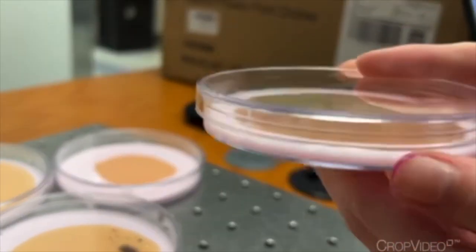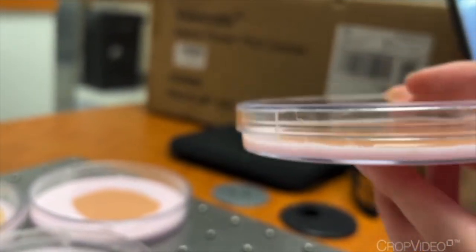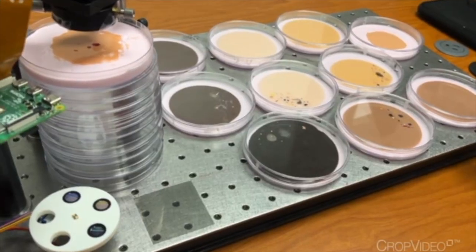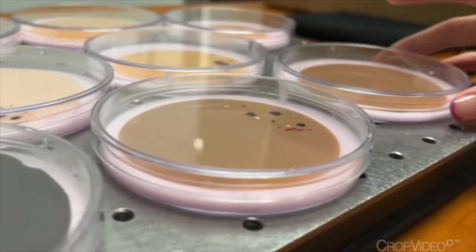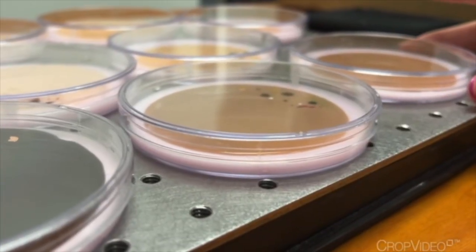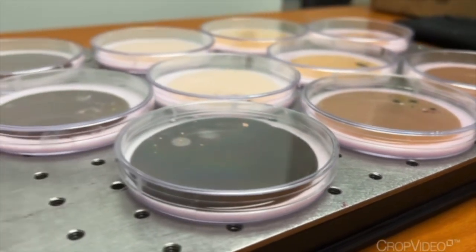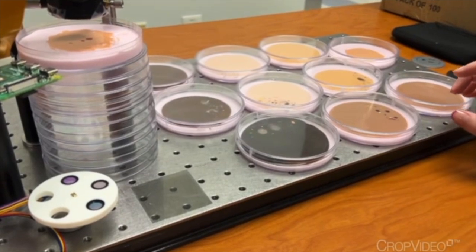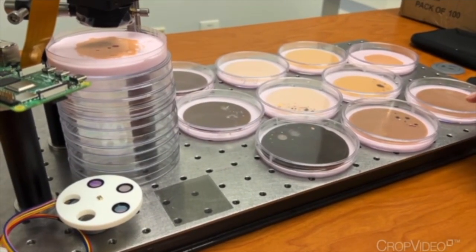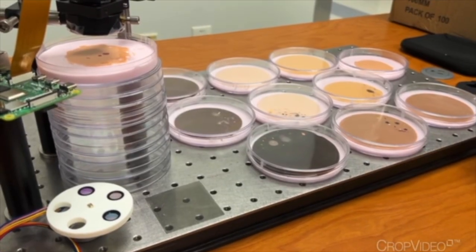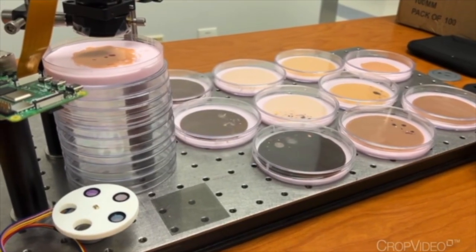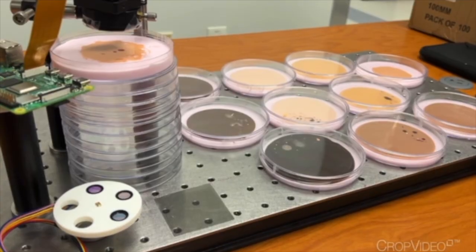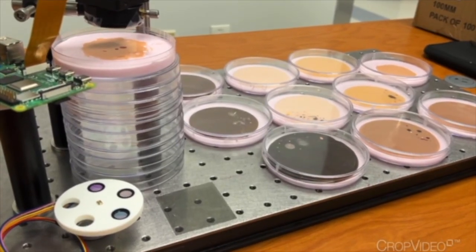So these are the two different layers. You can see a little bit more clearly the thicker, more translucent dermis layer on the bottom, which is the pink that you can see, is between 2 and 6 millimeters thick. Some samples also include small embedded channels designed to simulate subsurface blood vessels. This is important for optical imaging, so we can test the different wavelengths. For each skin tone, we casted samples at 1, 2, and 4 millimeters thick to prepare for reflectance and transmittance measurements using light-emitting diodes operating at 470, 530, 630, 850, and 940 nanometers.